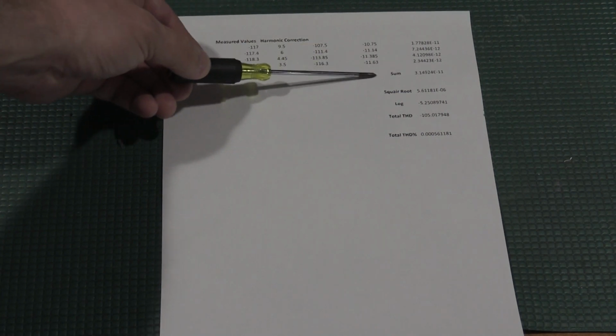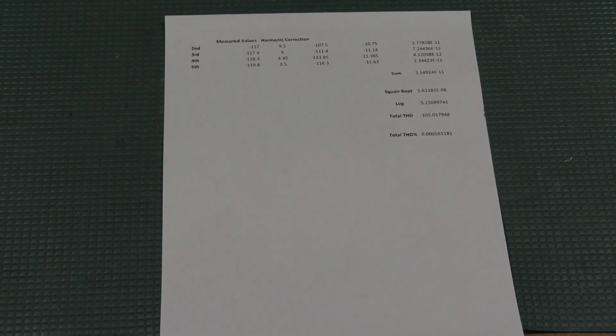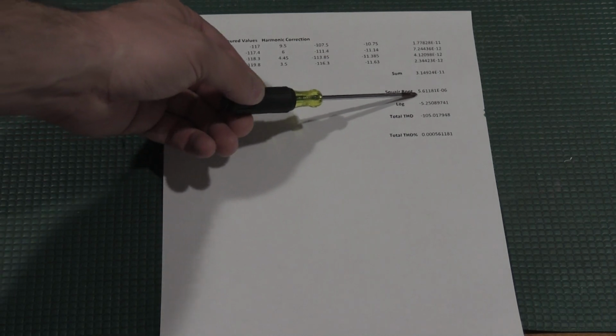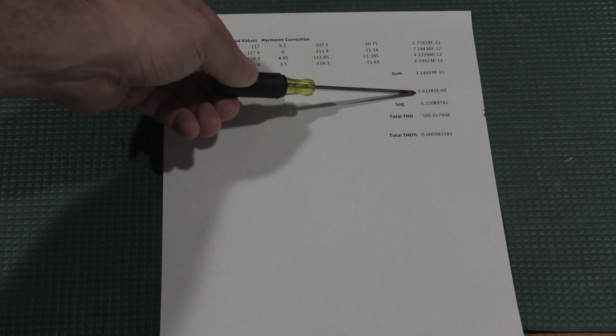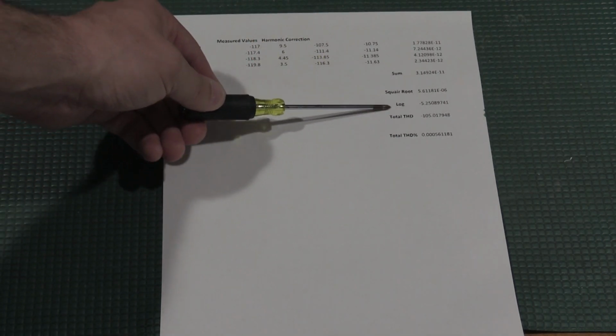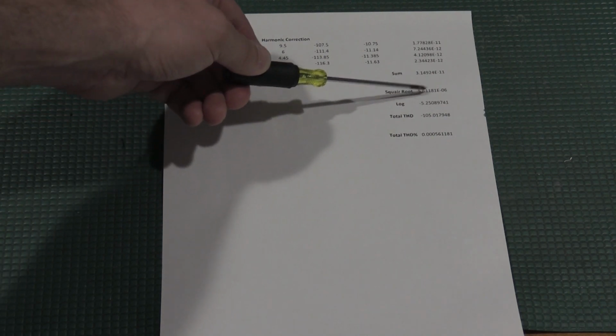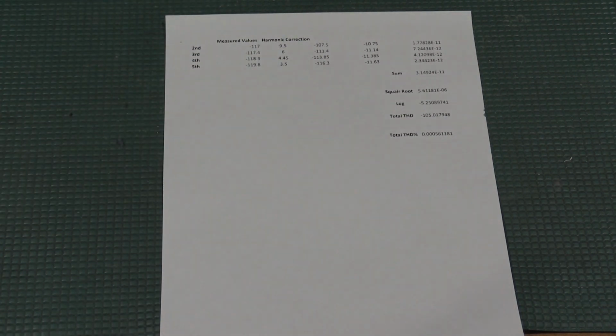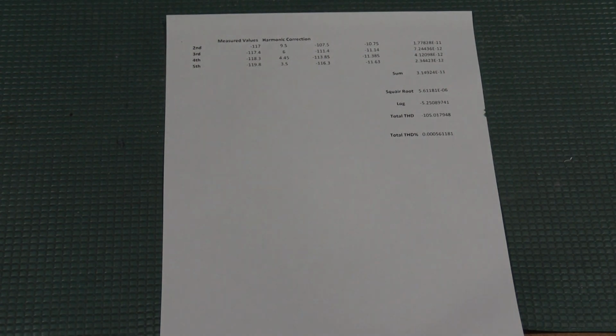We then sum those values, just straight addition. Take the square root of this number, which ends up being that number. We then take the log of that number, which ends up being that number. And that gives us our total THD in dB. On the 1 kilohertz frequency, we're going about -105.017948 dB. Fairly accurate. Well, at least that's what the numbers say.